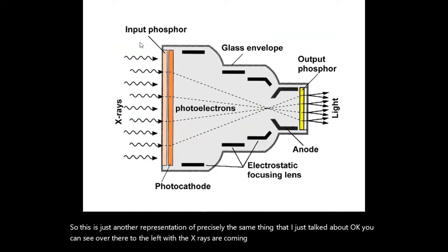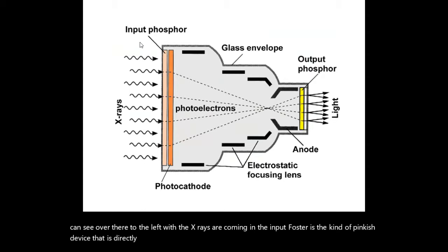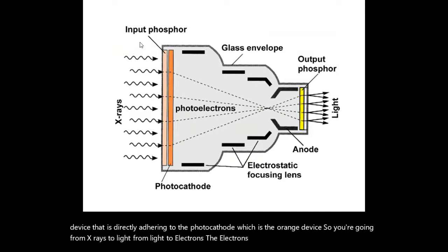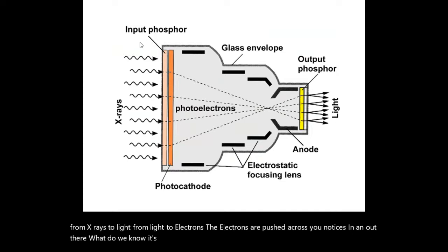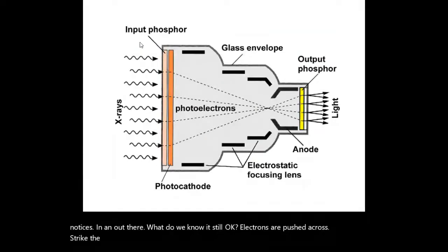The input phosphor is the kind of pinkish device that is directly adhering to the photocathode, which is the orange device. So you're going from X-rays to light, from light to electrons. The electrons are pushed across. You notice there's an anode there. What do anodes do?